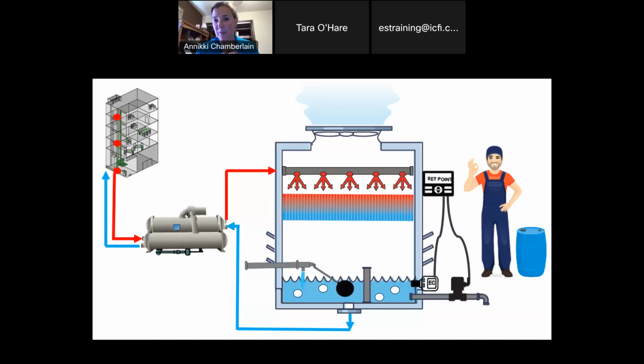They can always fail. We can have a controller failure, right? We could have a problem with the controller that's not sending signals to or from the sensor, or a sump heater failure. I've definitely seen recirculation pump failures, but yeah, any pump, basically any piece of equipment.